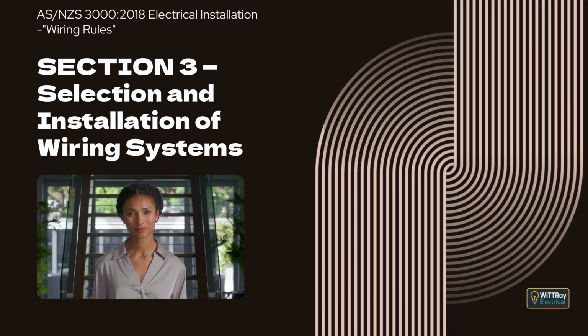This clause explains that aerial wiring systems are used where cables are supported above ground, and that their use may be restricted by local authorities in some areas, especially where there is a higher risk such as bushfire zones. Clause 3.12.1 Types of conductor. This clause states that conductors used as aerial conductors must be suitable for aerial use, and this includes hard-drawn bare conductors, polymeric insulated cables, neutral screened cables, and insulated conductors that are twisted, bundled, or arranged together for aerial installation.